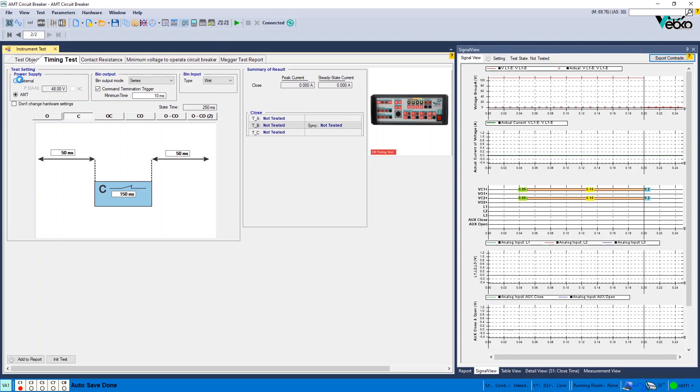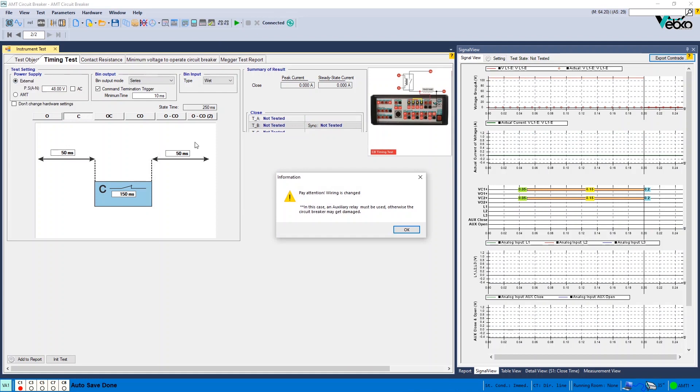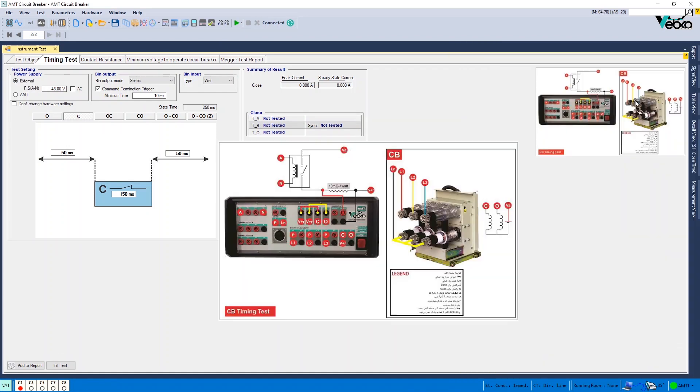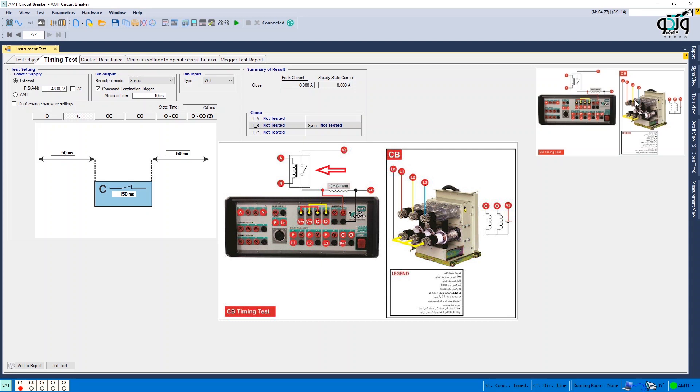In this case, check the external option and set the new wiring and start the test after pressing Init Test. If you are using an external source to provide the voltage of the bobbins to better protect the bobbins, put a glass relay with the binary outputs in series so that if something unexpected happens to the binary outputs which made them no longer able to disconnect the voltage applied to the bobbins, the CB is not damaged. And in this way, you can have more control on connecting and disconnecting the supply applied to them.